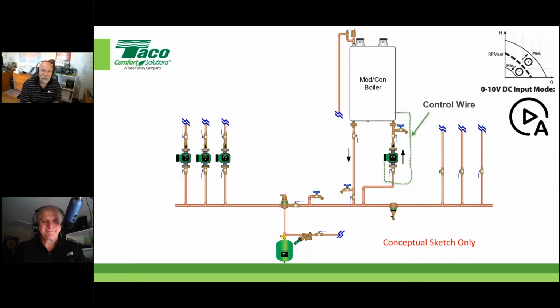Now, every boiler manufacturer might be a little bit different, and some of them at this point in time aren't giving you this control wire, and some of them are. So you have to look and see. I'm going to cover both ways of sizing the pump, and the sizing that we're going to talk about applies to both configurations. But we're just acknowledging the fact that nowadays we have these third-party signals, 0 to 10, that our circulators can receive. And then it's like Taco turns the keys over to the boiler manufacturer and says, hey, you run me at whatever speed is appropriate for this current condition. And that's a good thing. So take advantage of it if you can.